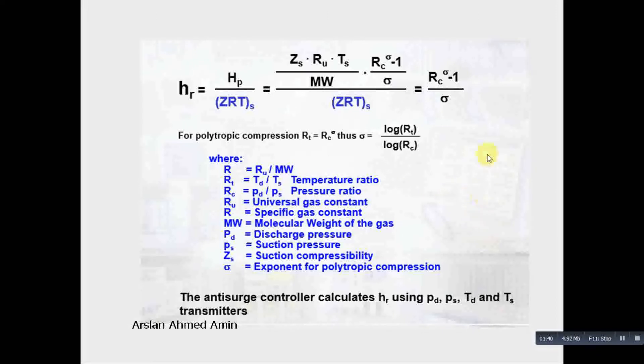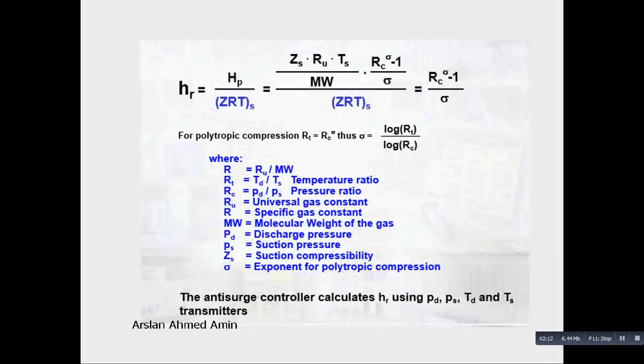This is how the compressor map is built, and this algorithm drives the anti-surge controller. The anti-surge controller can also use a PLC, but we normally use dedicated controllers for this application. The main reason for using a dedicated controller is that this involves only a single action, so for one action we normally use a dedicated controller.